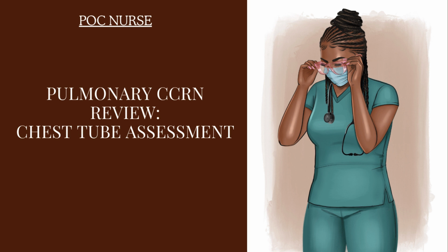The next part is the suction chamber. I just talked about suction a few minutes ago. So the suction chamber is where you would connect your wall suction. However, the wall suction does not control the suction that's happening within the box.